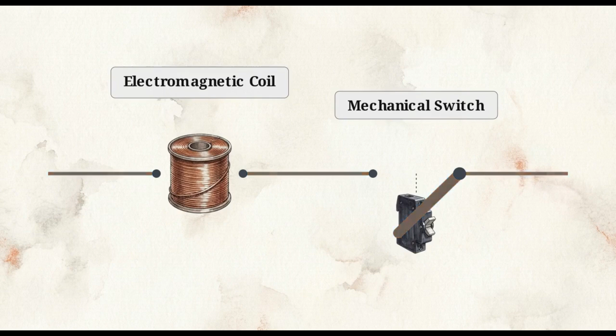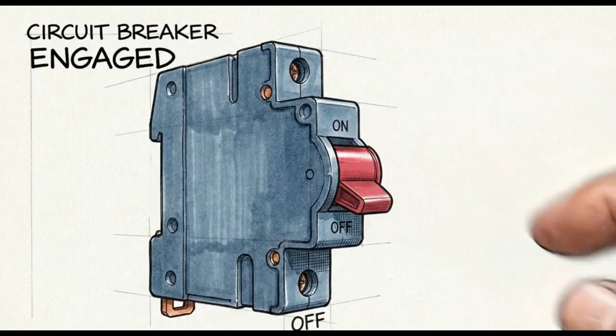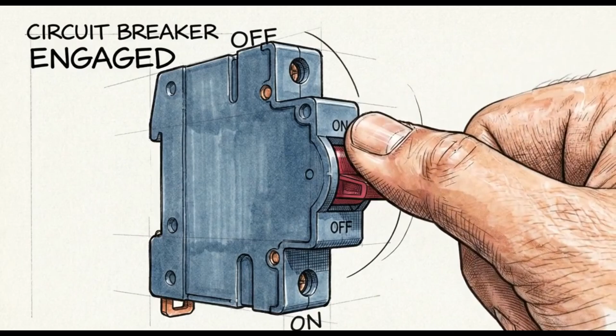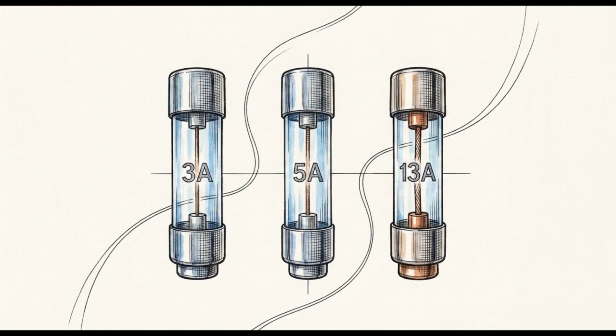Instead of a sacrificial melting wire, a breaker uses an internal electromagnetic coil placed right next to a physical switch. Electricity flowing through a coil naturally creates a magnetic field. When a massive, unsafe surge of power hits, that magnetic field spikes instantly. This creates a powerful magnetic shove that physically hits the switch and knocks it out of its connected position. The sheer force of that sudden magnetic field forces the switch open. The electrical path is broken and the electricity stops flowing immediately.